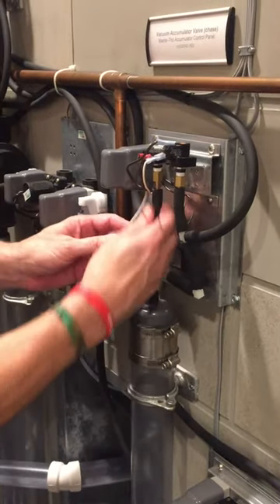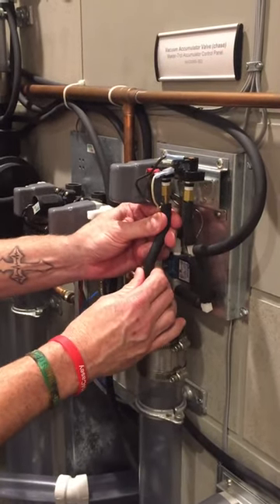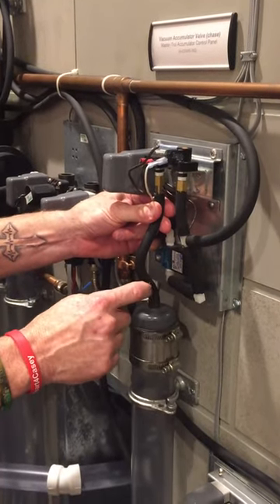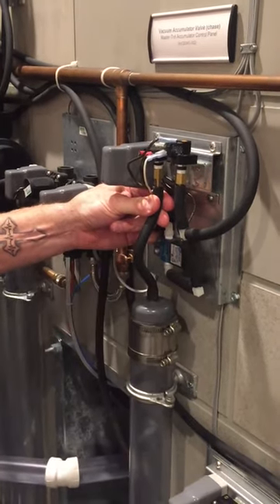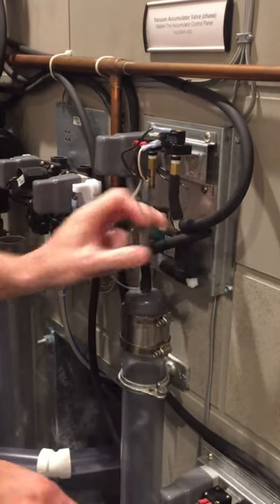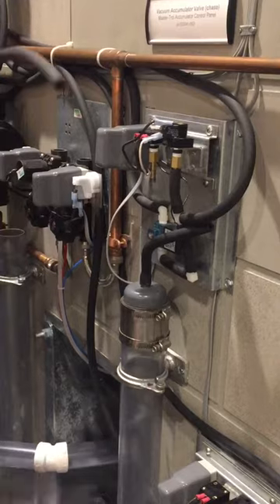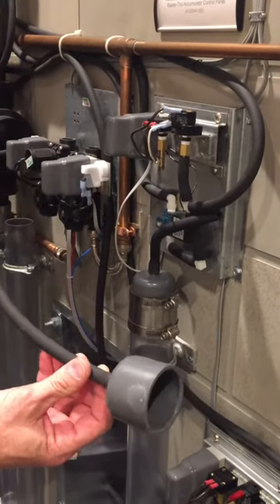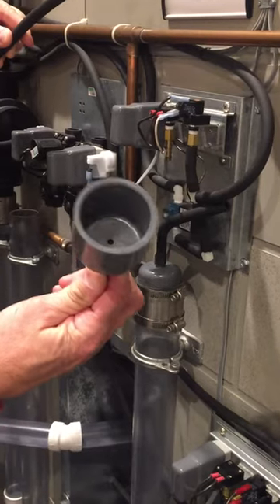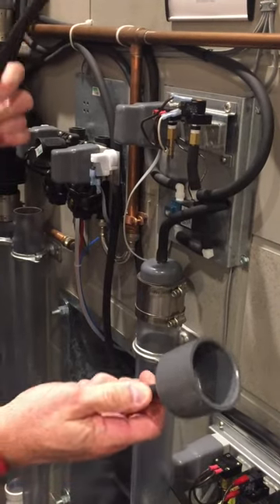The first step is to check the pressure switch by removing this hose that goes between the sensor port cap and the pressure switch. We're going to do what's called a dip test, which you should have one of these on site at the facility. It's just a gray sensor port cap and a length of hose.